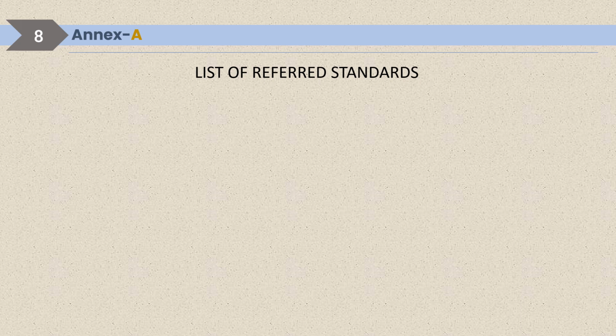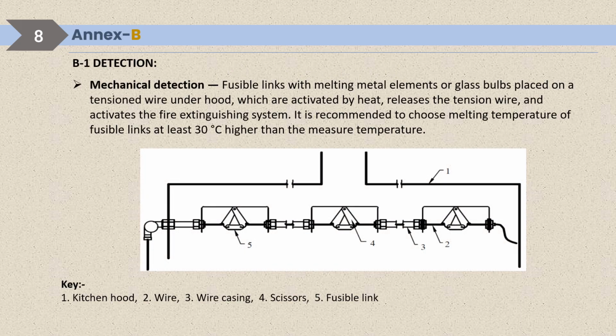Now we have reached the annexures. In Annexure A, as I already told you, the list of referred standards is mentioned. Annexure B is talking about the detection, so how the fire suppression system works. Mechanical detection: fusible links with melting metal elements or glass bulbs placed on a tension wire under the hood, which are activated by heat, release the tension wire and activate the fire extinguishing system. It is recommended to choose a melting temperature of fusible links at least 30 degrees centigrade higher than the measured temperature. So this type of arrangement you will see in mechanical detection of a fire suppression system with fusible link.